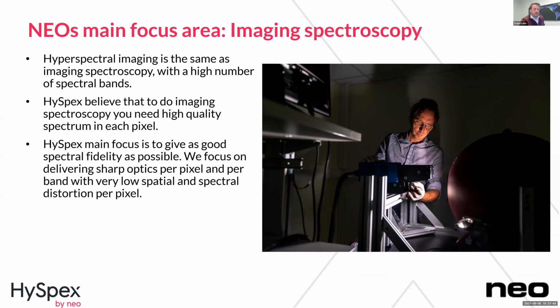I think about 5 years ago, imaging spectroscopy moved into being the main focus area of NEO. And hyperspectral imaging is the same as imaging spectroscopy, just with a high number of spectral bands. We believe that to do imaging spectroscopy, you need high quality spectrum in each pixel. So HySpex main focus has been and always will be to deliver as good spectral fidelity as possible. So with the focus on delivering sharp optics per pixel and per band, and with very low spatial and spectral distortions per pixel.